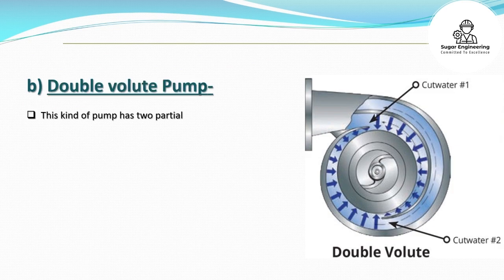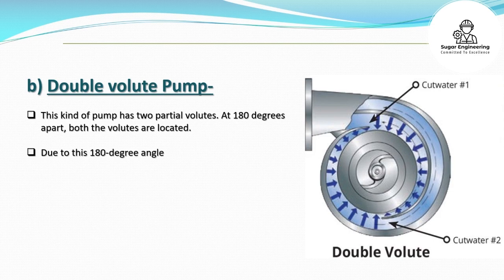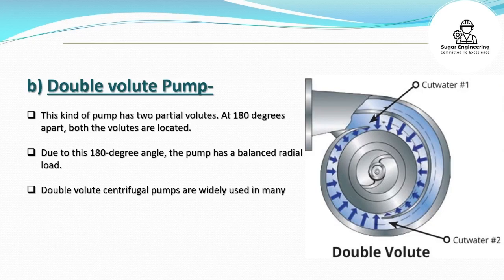B. Double volute pump. This kind of pump has two partial volutes located 180 degrees apart. Due to this 180-degree angle, the pump has a balanced radial load. Double volute centrifugal pumps are widely used in many industries.